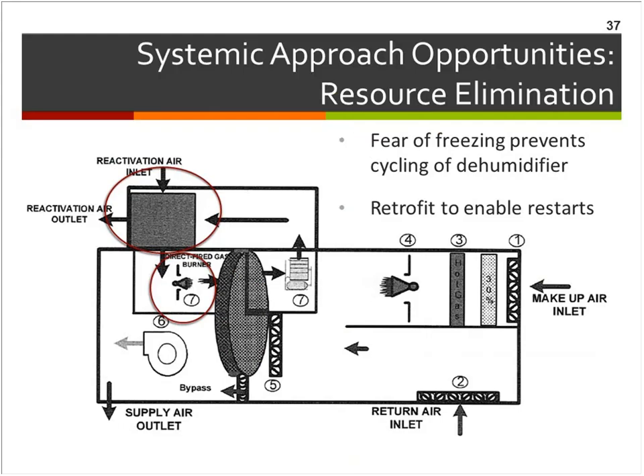Another brief example: it's a complex diagram, but the takeaway is that this is a dehumidifier with a flame—the small circle—that fires on that wheel at all times. Dehumidification is the purpose of this equipment, and it's rarely needed in the winter. So at this facility in the winter we asked, why is this on, and why is this flame still burning on the wheel? The reason was they were afraid to turn it off, because they worried it might freeze up their heat exchanger, the larger circle.